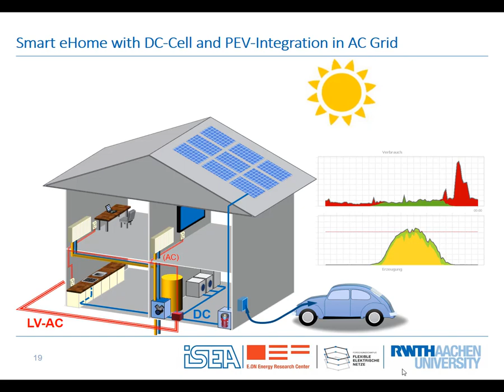Look at this typical street in Aachen with about 60 households total. Transformers are sized assuming each household takes an average peak power of 3.6 kilowatts, giving a typical connection capacity of 43 kilowatts, enough to charge your car at 20 kilowatts. But if everyone had a 20 kilowatt charger and plugged in at the same time, we'd have a big problem, because then we'd need 630 kVA of power.